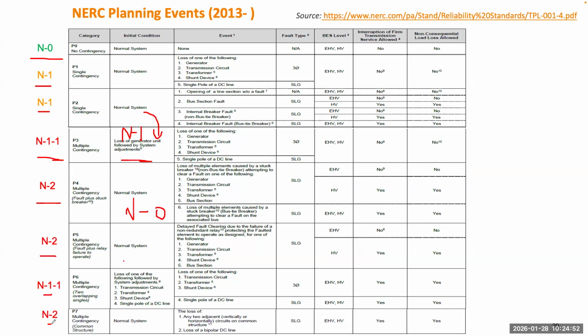So there will be more detailed situations for any contingencies. You may ask, what if the system loses more than two elements? Usually they will use terminology like N-3, or they just simply put N-K, where K can be any number bigger than 2. So that can be considered. Some utilities definitely need to meet all requirements in this table.